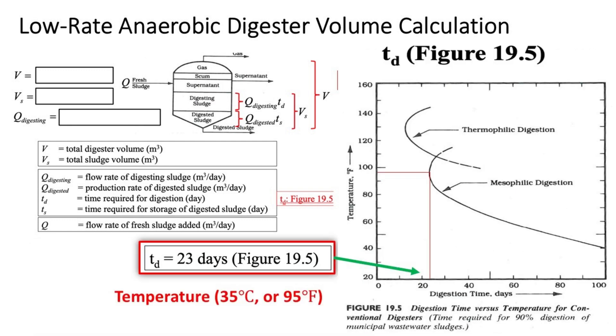Once fresh sludge enters the digester, it decomposes through anaerobic digestion. The digestion time TD is directly related to the activity of anaerobic microorganisms, and temperature is a decisive factor. Higher temperatures favor microbial activity. In this problem, the operating temperature is 35°C (approximately 95°F). Using a graphical solution, the digestion time TD is estimated to be 23 days.